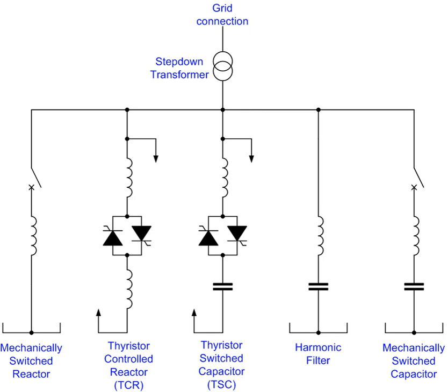If the power system's reactive load is capacitive leading, the SVC will use thyristor-controlled reactors to consume VARs from the system, lowering the system voltage. Under inductive lagging conditions, the capacitor banks are automatically switched in, thus providing a higher system voltage. By connecting the thyristor-controlled reactor, which is continuously variable, along with a capacitor bank step, the net result is continuously variable leading or lagging power.